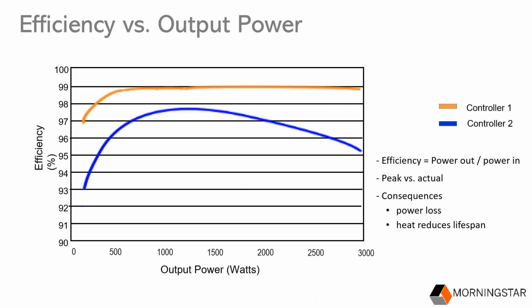Efficiency is a ratio of controller output power to input power from the PV array, or another way of looking at it is how much power is lost by the controller in the form of heat because of inefficiencies. You can see on this MPPT controller graph of efficiency versus output power that the Morningstar controller, represented by the orange line on top, provides significantly higher efficiency at both low and high output power levels.